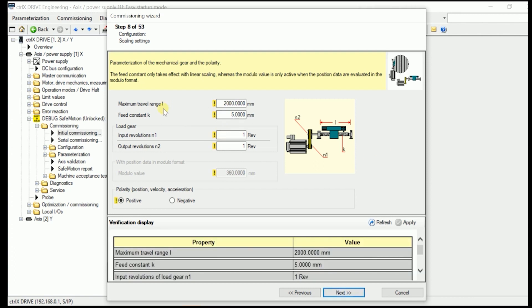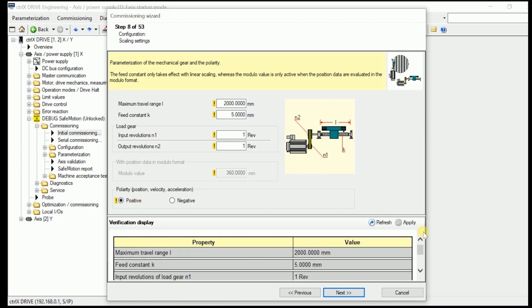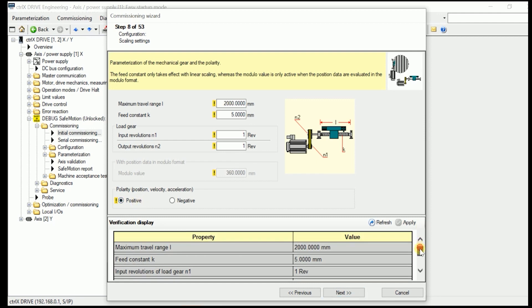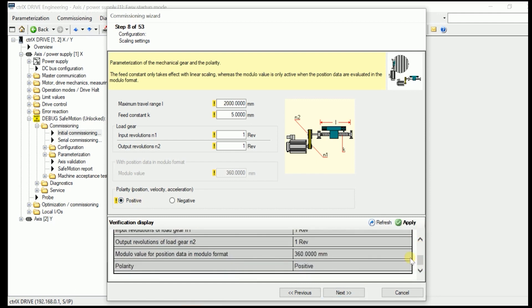By pressing next we come to what was taken over from the standard firmware. Like the maximum travel range, the feed constant, the gear ratio in here. If it's a modulo or absolute format axis. If we go from the polarity, positive or negative. Which were already established in the standard firmware. Now we apply these figures in here.